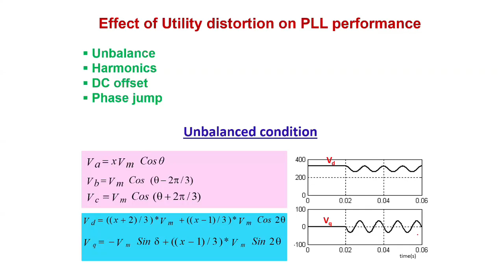The effect of utility distortion on PLL performance - he considered indices like unbalance, harmonics, DC offset, phase jump, and so on. He considered how these affect performance. The unbalance he created with respect to the phase A terminal, and the corresponding VD and VQ are represented. Here you can see the shape of VD and VQ - definitely theta is going to change, and the control will not be as expected.